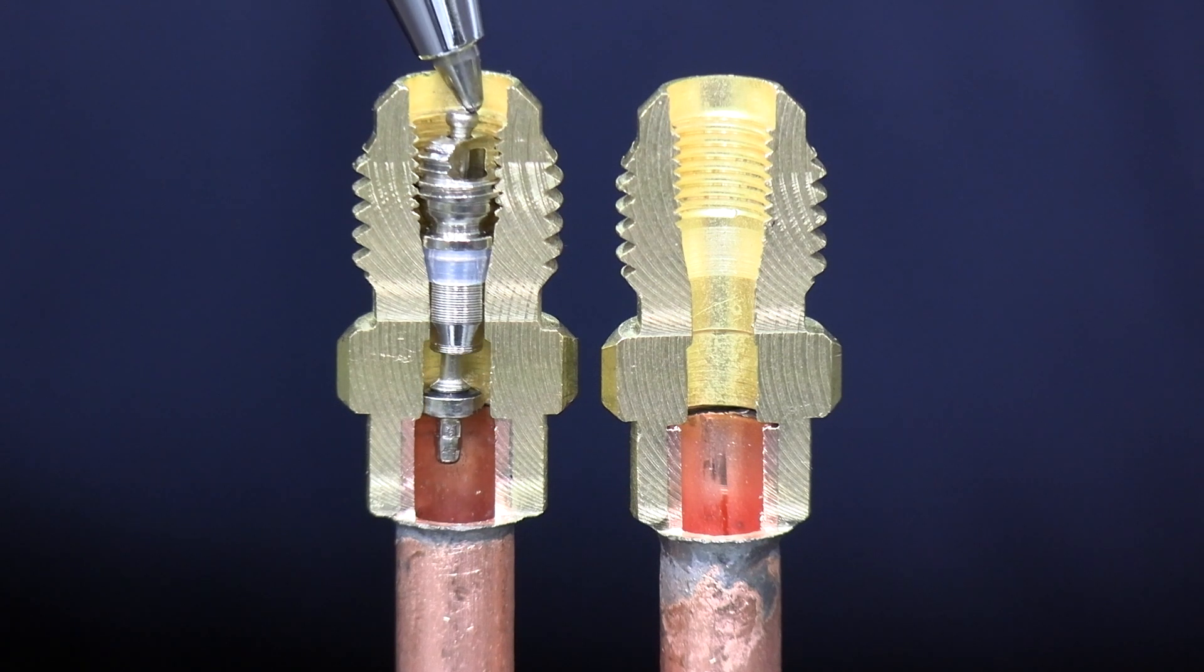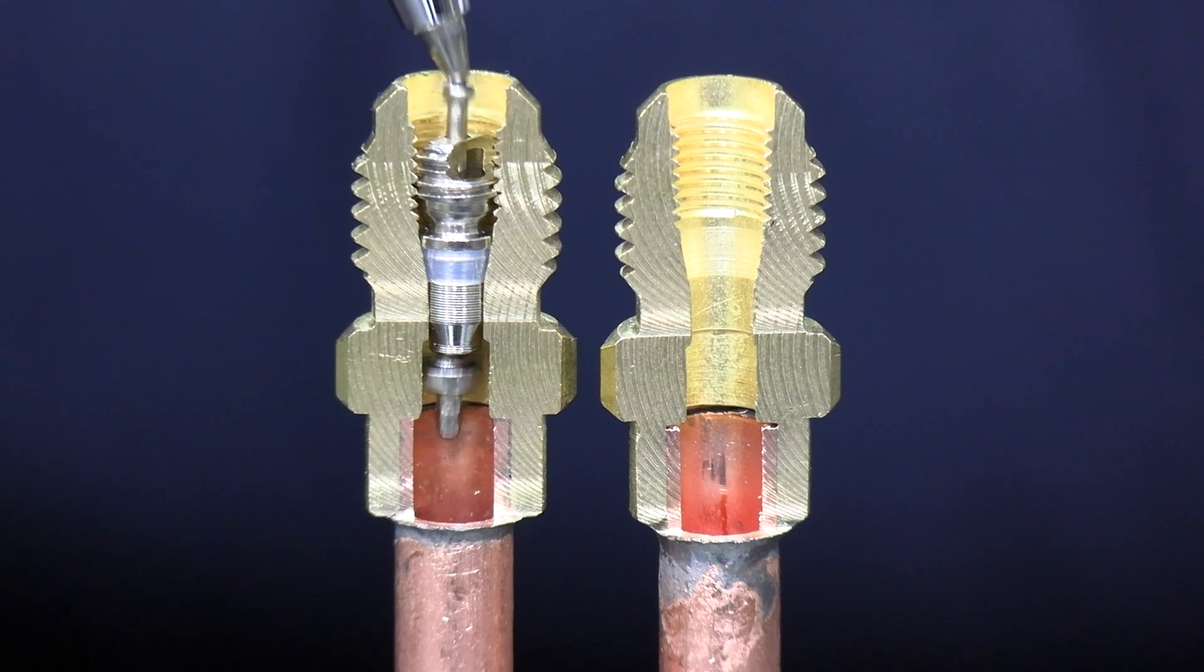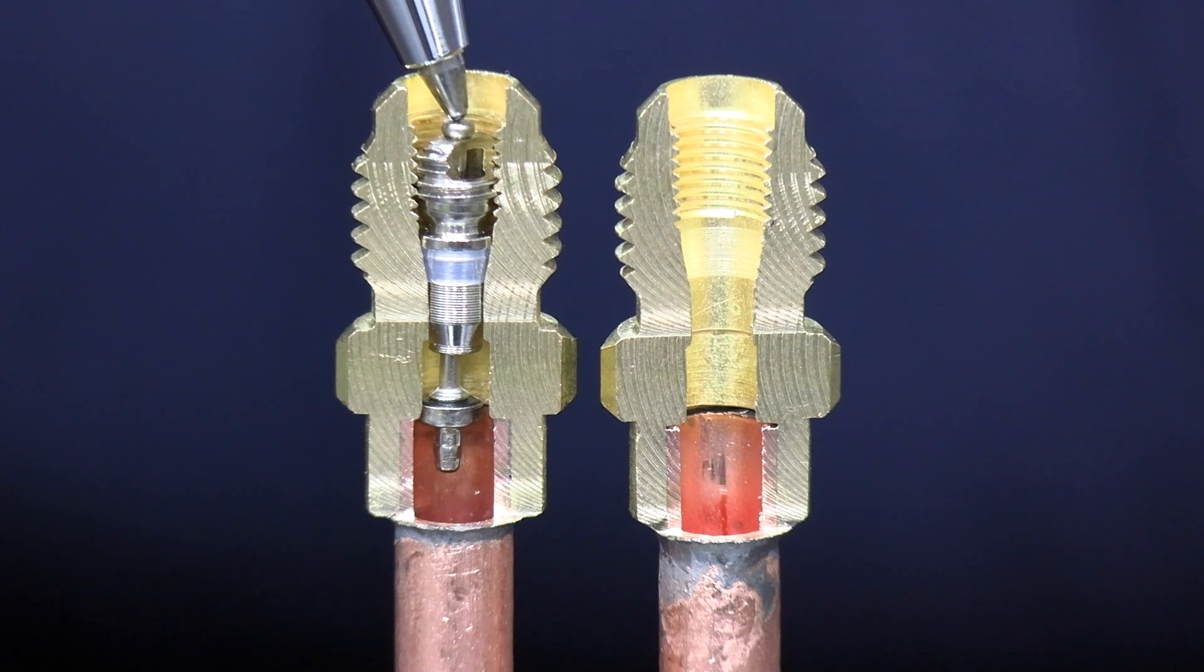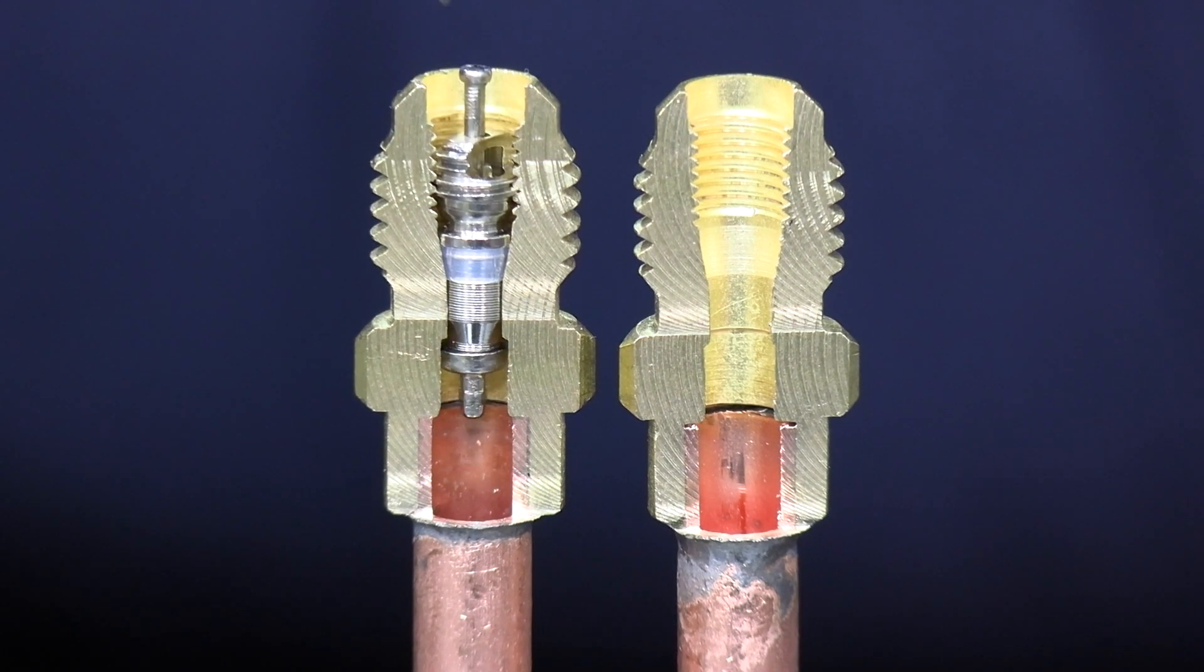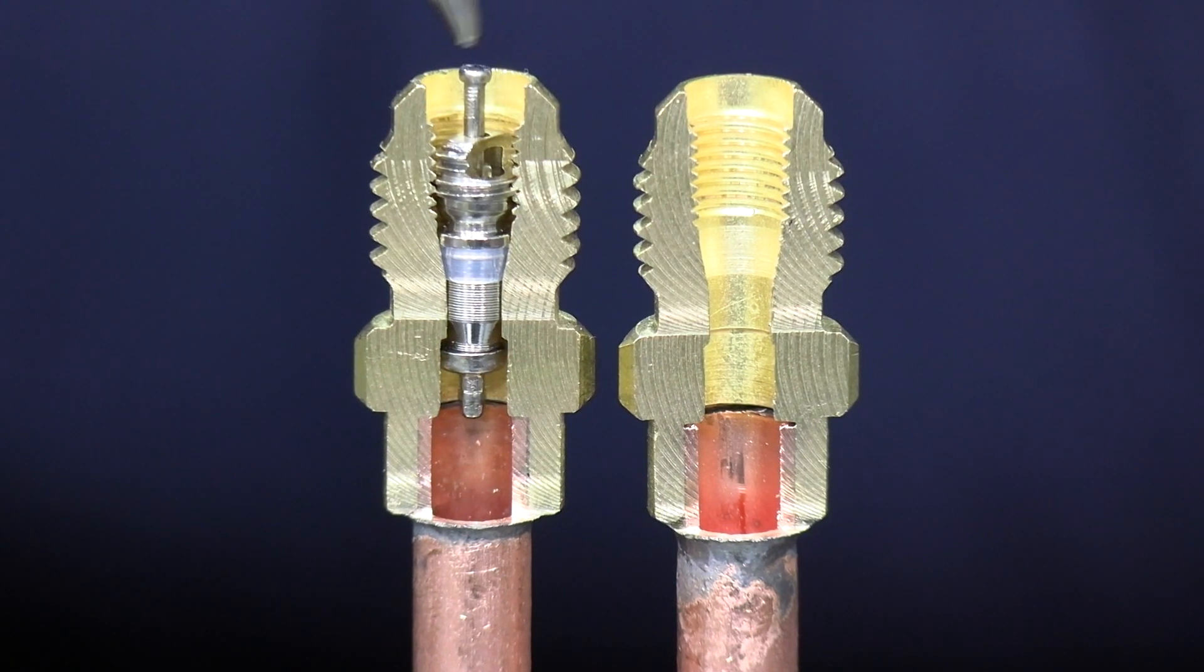you can see where the refrigerant flows through. You can see why it takes forever to evacuate systems leaving the Schrader core in there and why it's incredibly slow recovering refrigerants. Couple that with using quarter inch hoses which only ever give you 0.5 CFM vacuum flow through them anyway, and you can see why it takes forever to actually evacuate a system.